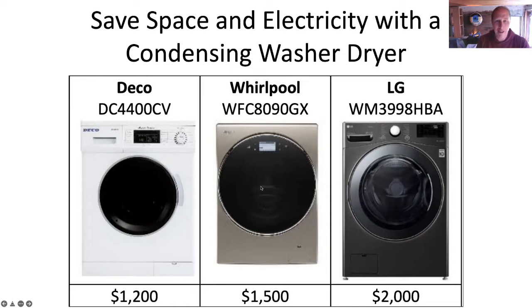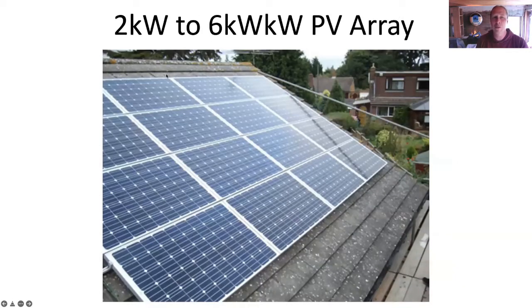So the last thing I wanted you to think about is you should put 2 to 6 kilowatts on your roof. On a 100 amp panel like you have, you can't do more than 6. You'll have to go to a 200 amp panel or something larger than the 100 amps you have, because solar is constrained to 3.8 kilowatts unless you have a fancy inverter, which would allow you to go up to 6 kilowatts. Basically, you can't put more than 3.8 kilowatts of electricity into the grid with your 100 amp panel. So 2 kilowatts, you shouldn't do less than that because you already have someone up on the roof, and you can't really do more than 6 kilowatts. 3.8 is right on the nose if you don't want anything technically challenging.